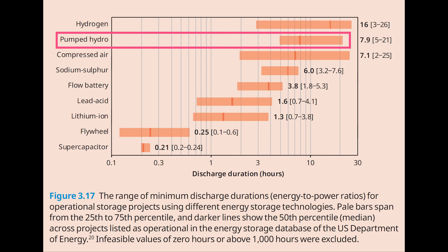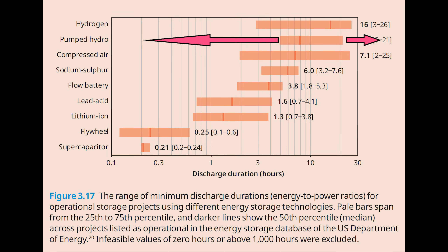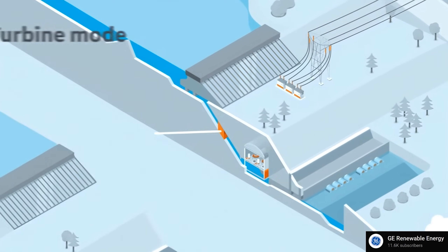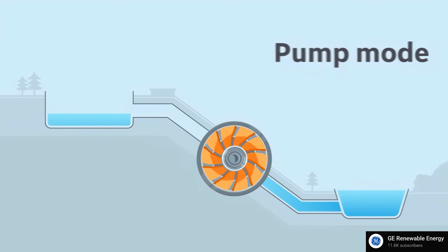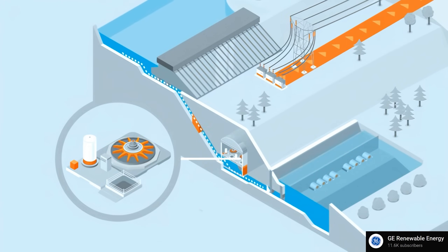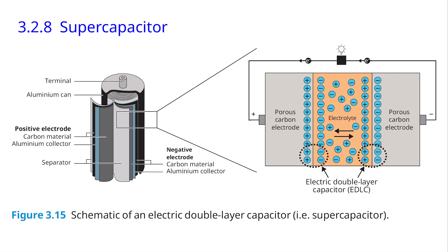To further explore cost efficiency, let's again use pumped hydro as an example. Pumped hydro reservoirs can be made larger to increase energy capacity, and more or larger turbines can be used to increase power capacity. So why not just use pumped hydro for every duration? In the case of short durations in the range of minutes, emptying and converting a lake-sized reservoir to power that quickly wouldn't be cost efficient. Turbines are expensive, and they need to run as much as possible to lower the capital cost per unit of power generated. Usually, pumped hydro runs during off-peak periods to fill the upper reservoir over several hours, and then discharges over several hours during peak periods. If it discharged in a few minutes, that would require more turbines — which are the primary expense — and then the turbines would sit idle for hours a day not generating revenue. For shorter durations, it's better to use a technology with a lower energy-to-power ratio that can convert energy to power more cost-efficiently.